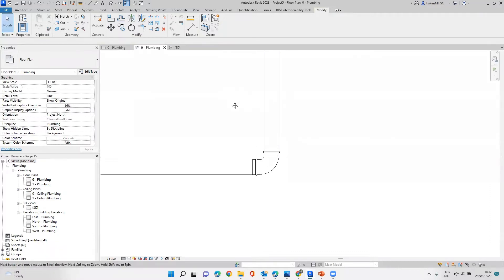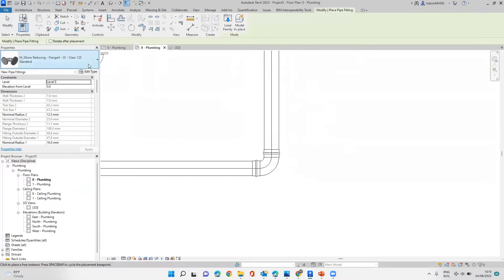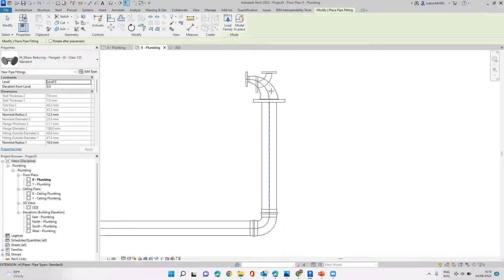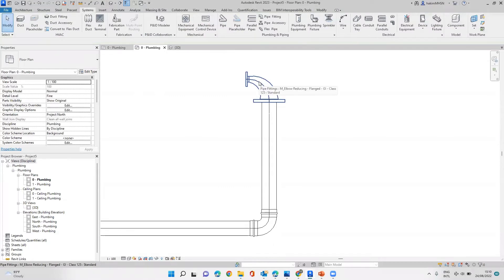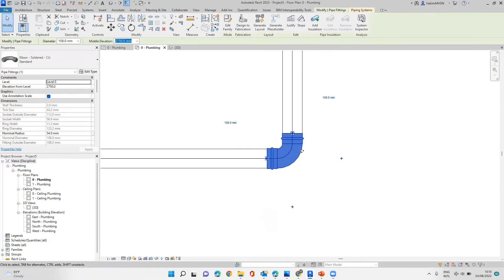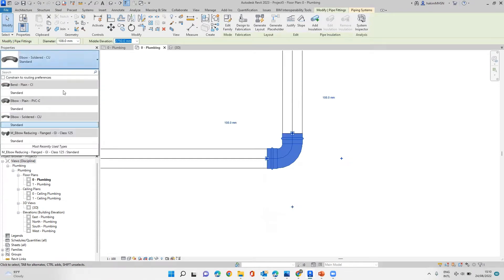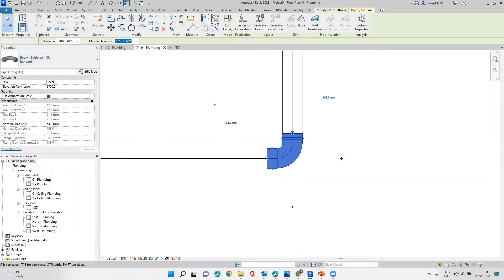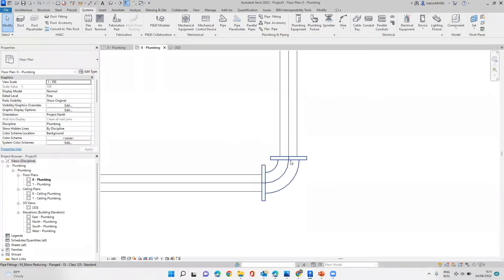Now Revit will ask you to place the fitting right away, but I don't need to do that. I can just press Escape — what's important is it's already in our project environment. To place it, I can go to Systems, Pipe Fittings, choose it, and then place it. As you can see, it can detect automatically. To replace an existing elbow, click the existing one, go to properties, drop down, and you will find the one you loaded in — M Elbow Reducing Flange GI Class 125. Just click on it, and you can see the new elbow replaces the old one.